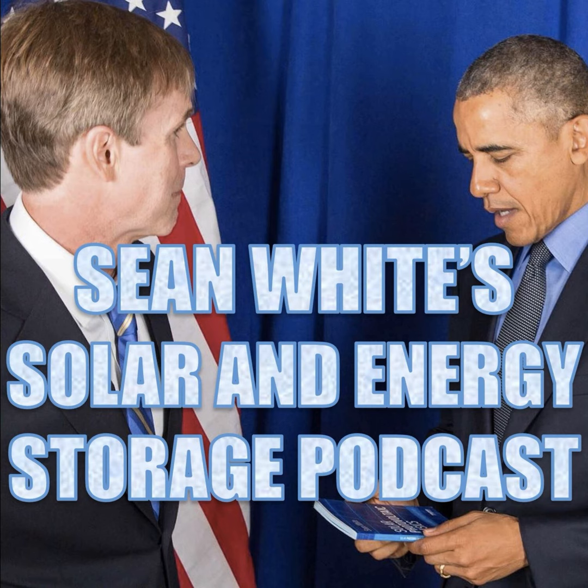It's coming out of your power source, so it's coming out of your interactive inverter. And remember that Article 705 doesn't just cover energy storage systems, it also covers solar inverters. Just think of any kind of inverter that could put electricity back on the grid. So it's those conductors that are going out to your service or distribution equipment. Distribution equipment is oftentimes going to be a load center, which could also be called a main service panel or a subpanel, or a panelboard.